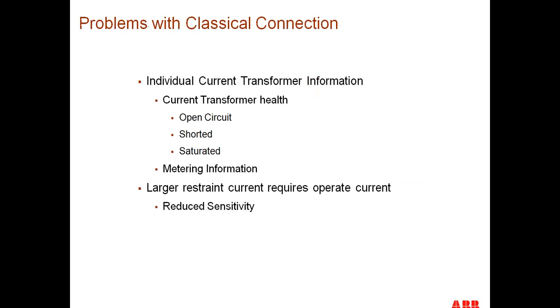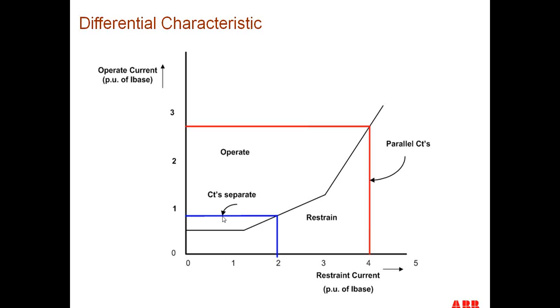Okay, so now we not only lose metering information, but we also get the larger restraint current. Because we're adding two currents together, coming into one input to the relay, we have a much larger restraint current than we would have had if we kept these two currents separately. Therefore, we reduce the sensitivity of the relay. Here's an example we're talking about.